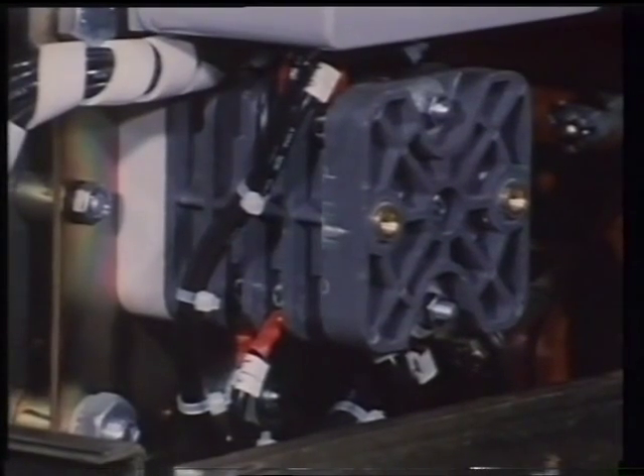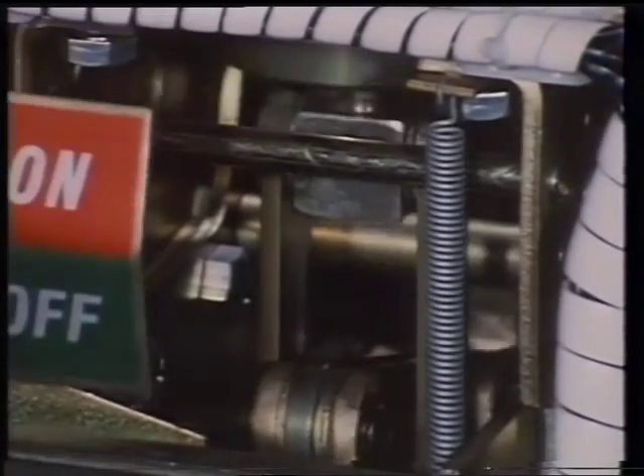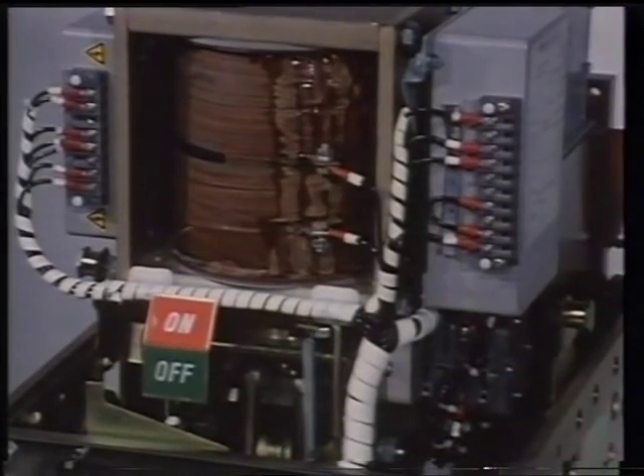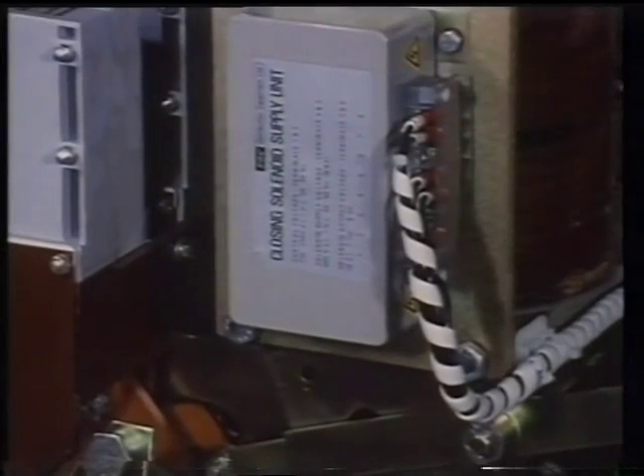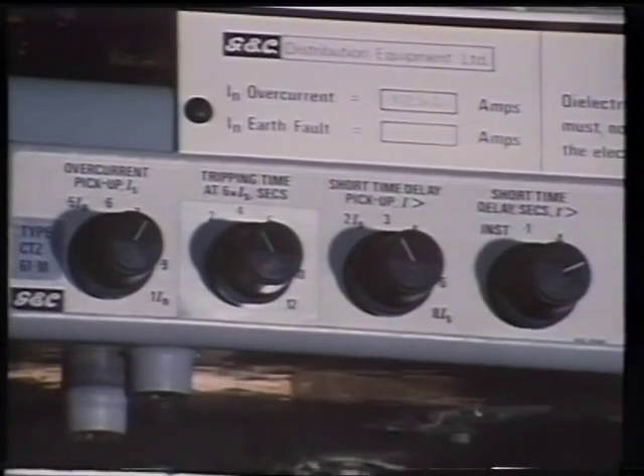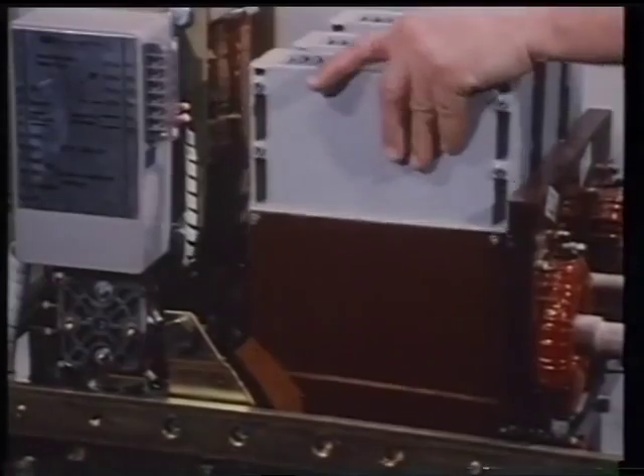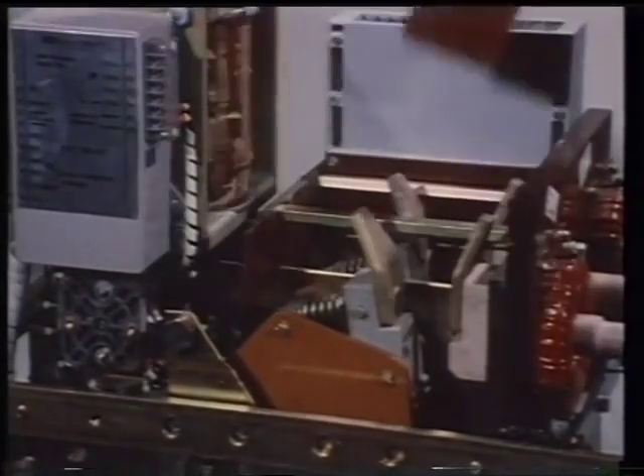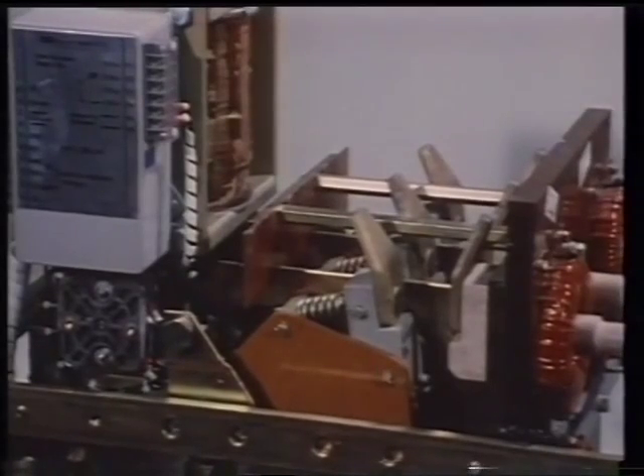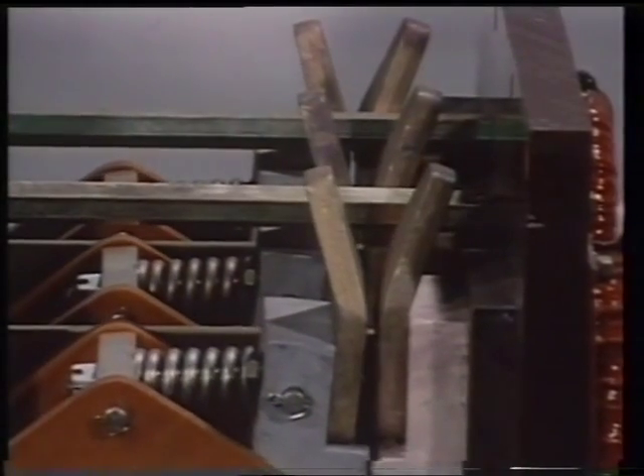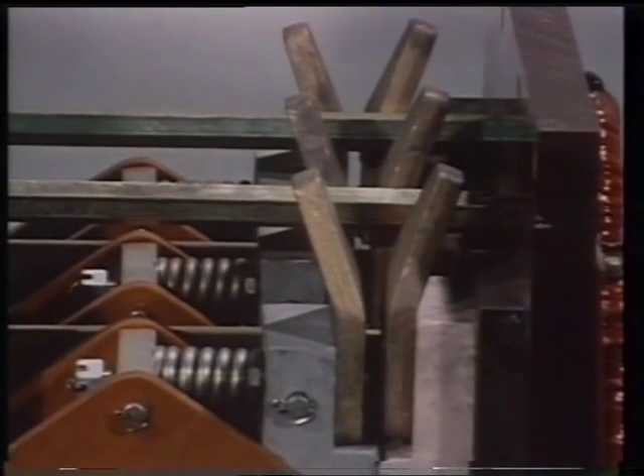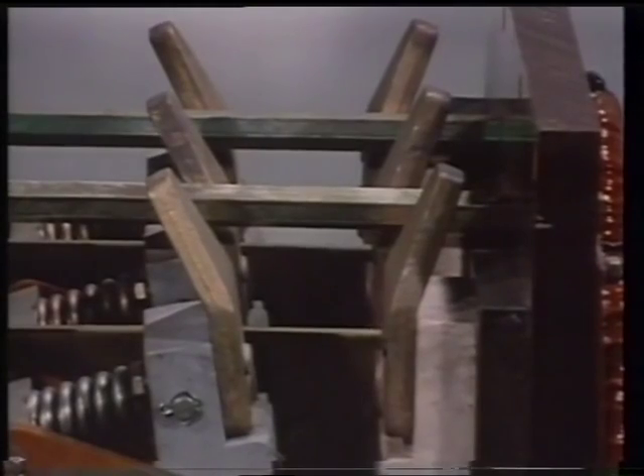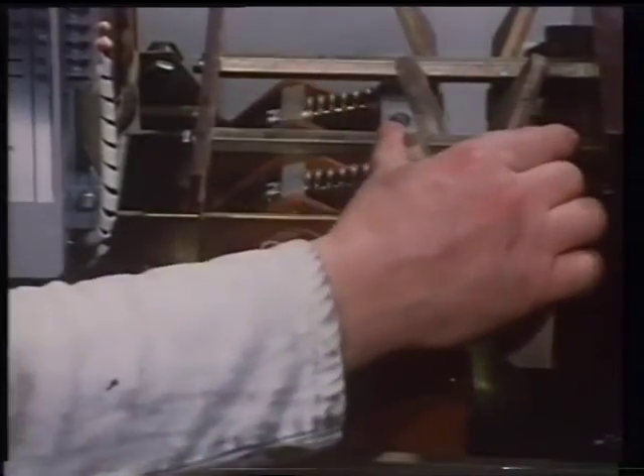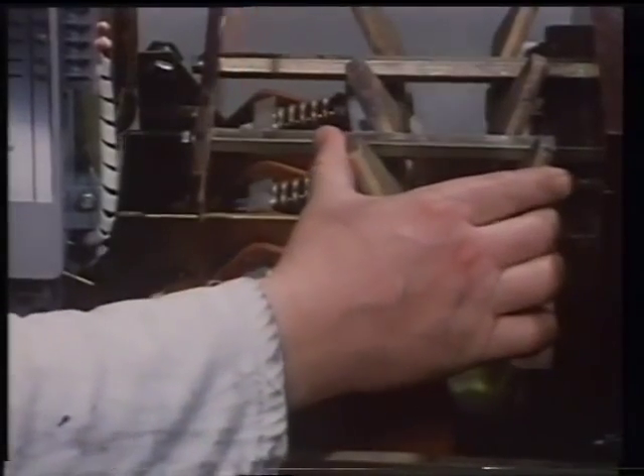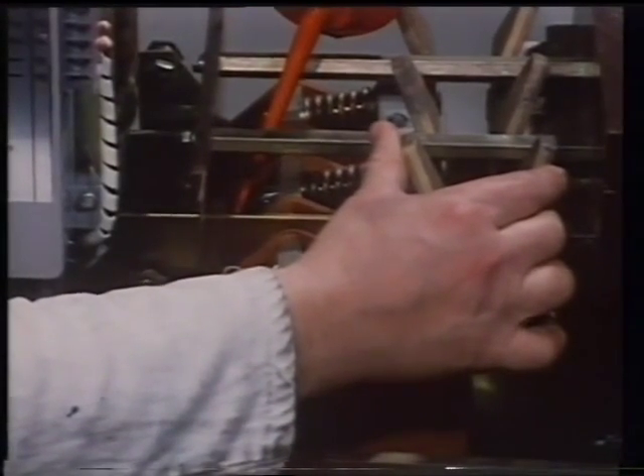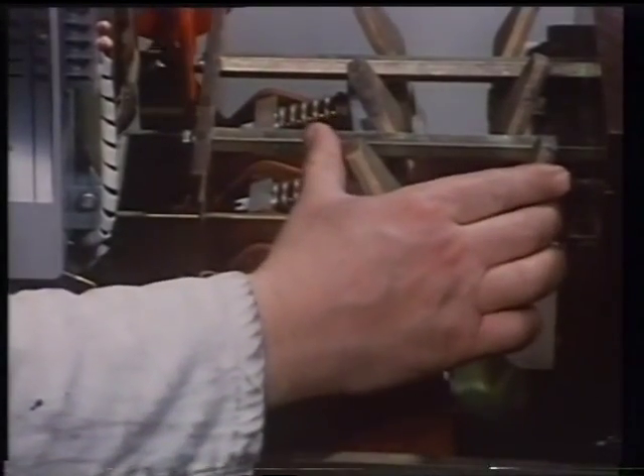A set of auxiliary contacts, the closing link mechanism, the closing coil solenoid, overcurrent relay, and a set of fixed and moving main contacts with their arc chutes. The main contacts are closed under spring pressure, which wipes the surface of the fixed contact points, ensuring good electrical contact. These contact points are plated and must not be greased or cleaned with abrasive material. Generator circuit breakers are set for correct function at the factory. By way of routine service, all moving parts should be lightly oiled.